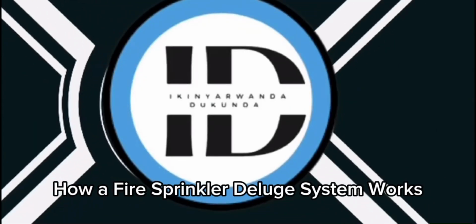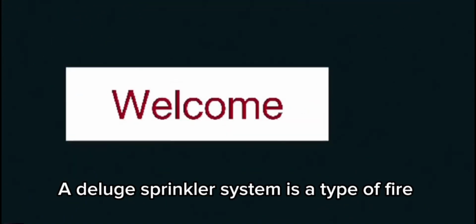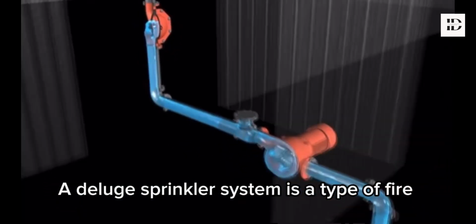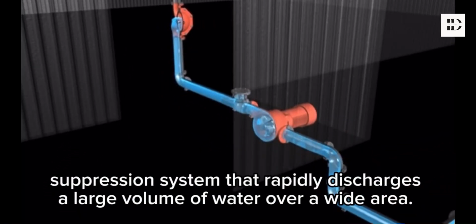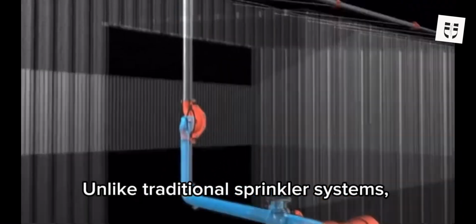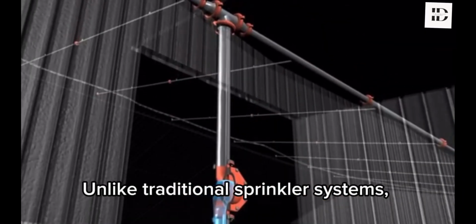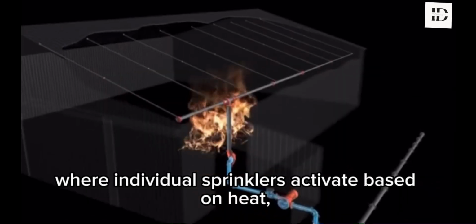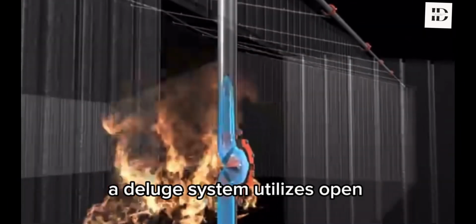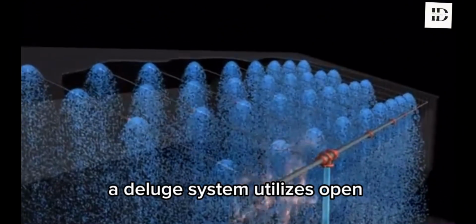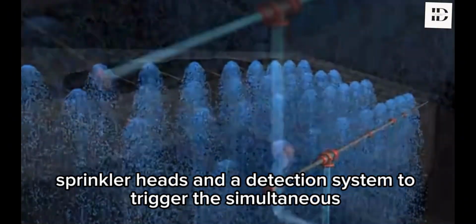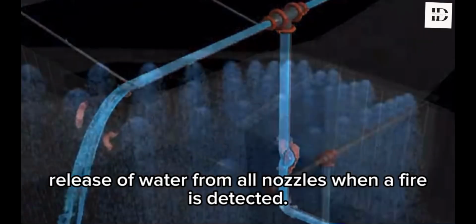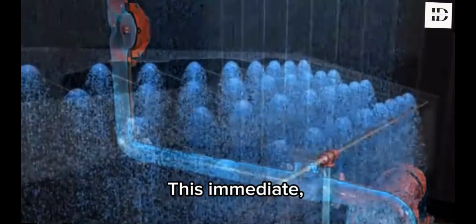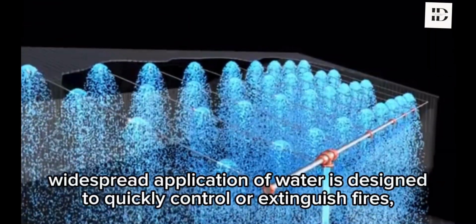A deluge sprinkler system is a type of fire suppression system that rapidly discharges a large volume of water over a wide area. Unlike traditional sprinkler systems, where individual sprinklers activate based on heat, a deluge system utilizes open sprinkler heads and a detection system to trigger the simultaneous release of water from all nozzles when a fire is detected. This immediate, widespread application of water is designed to quickly control or extinguish fires, particularly in high-hazard areas where rapid fire spread is a concern.